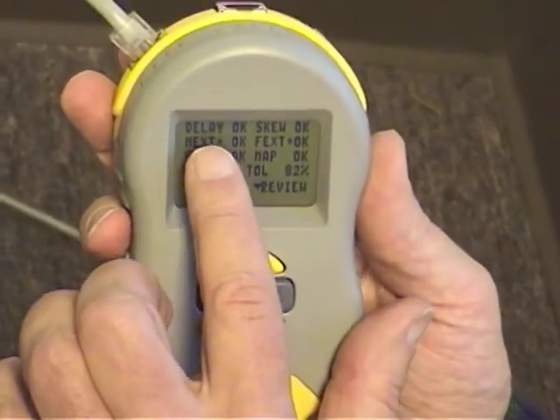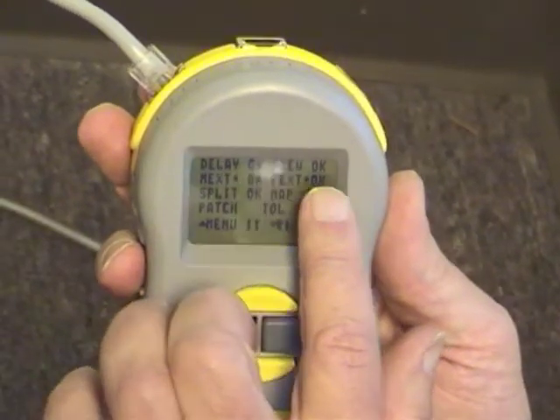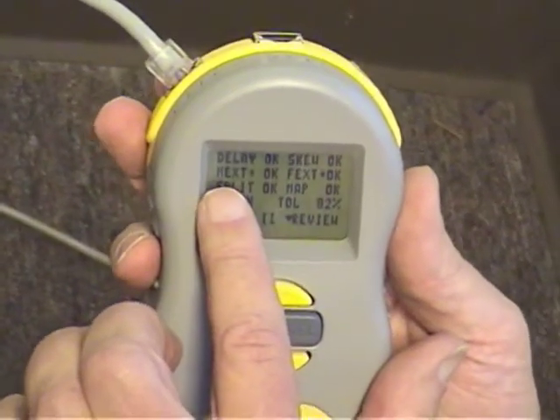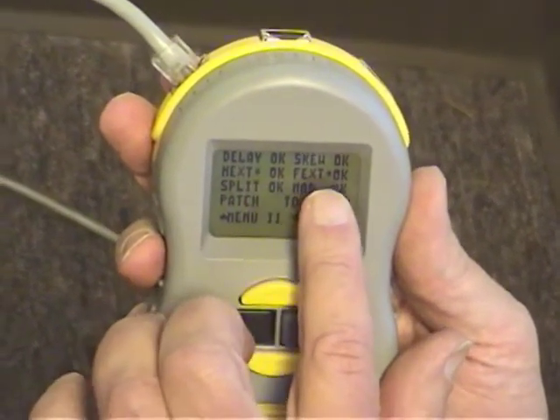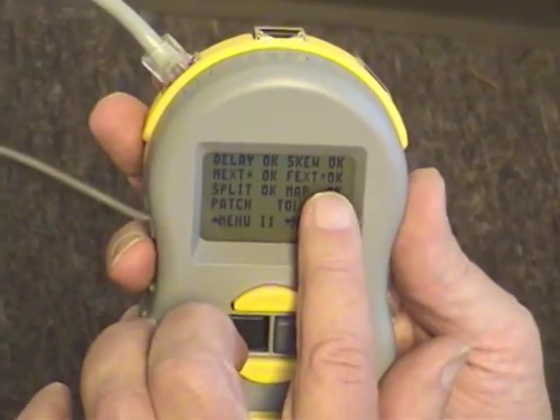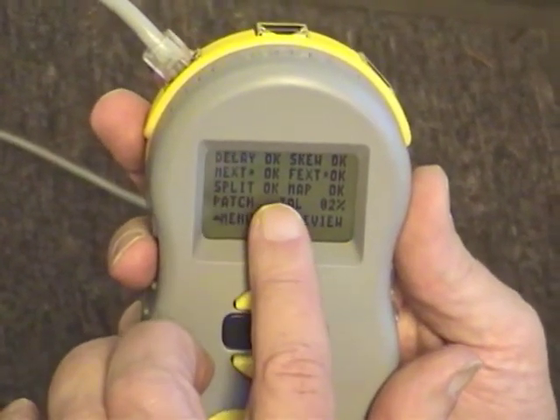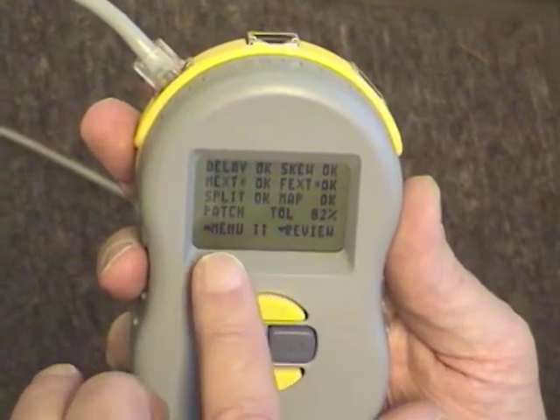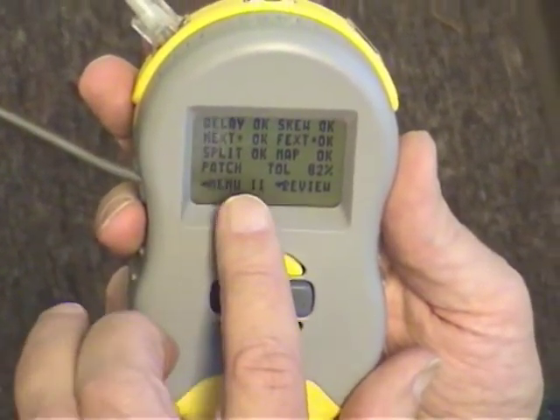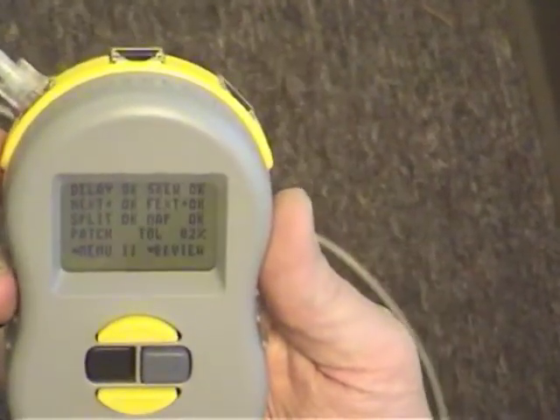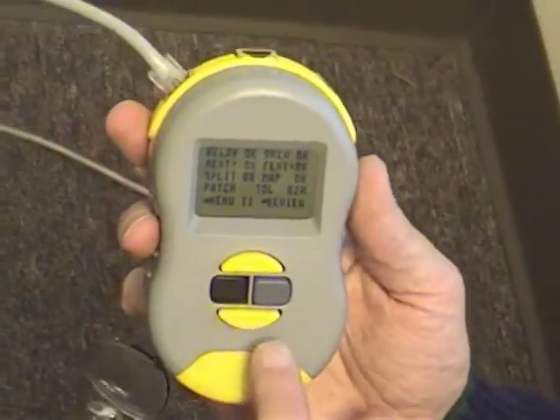It tells us that the delay is okay, it's in spec. The skew is in spec. The near end crosstalk is okay. The far end crosstalk is okay. There's no split pairs, and the map is good. It's a patch cable with a tolerance of 82%, which is our margin - very good.